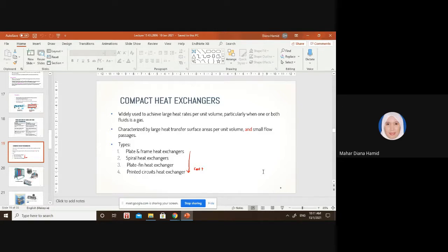So as we move down from 1 to 4, the cost of these heat exchangers increases. In order for you to use the printed circuit heat exchanger, you must have a good reason for it. Usually, we only use printed circuit heat exchangers for oil and gas industries because the cost is very high. One printed circuit heat exchanger would cost at least 1.5 million ringgit. So that's why we don't really use them.